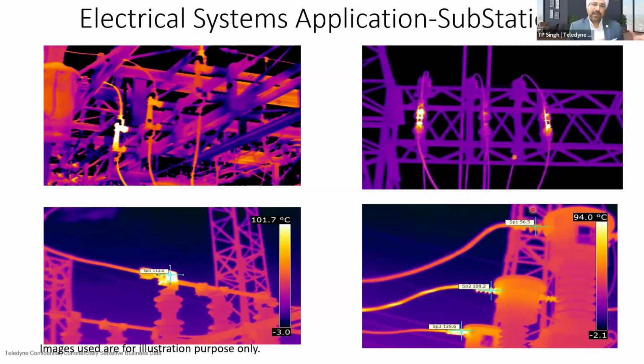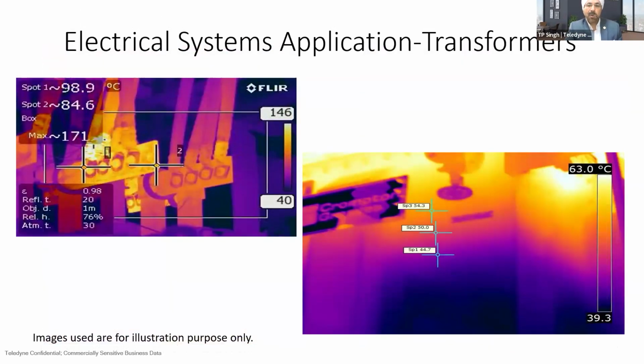This means whether it is a wave trap or a fuse or a CT, PT, bushing of a transformer, or even a transformer itself, everything can be viewed very easily and can be documented as well. This is the image of a transformer wherein the bushings are having a problem. Even in a healthy transformer, from top to bottom there is generally a 25 degree centigrade variation because the oil moves from up to down, and that's how you can at least visualize whether the transformer is having any problem or not.